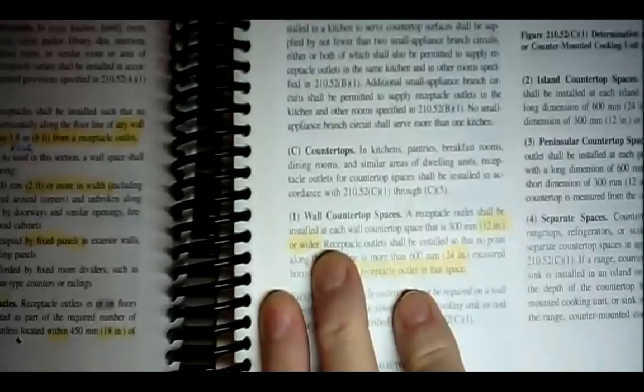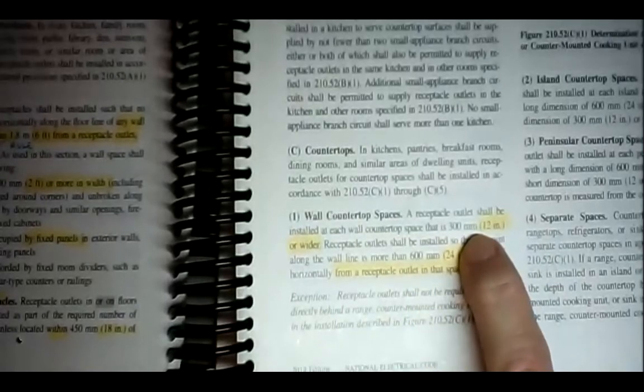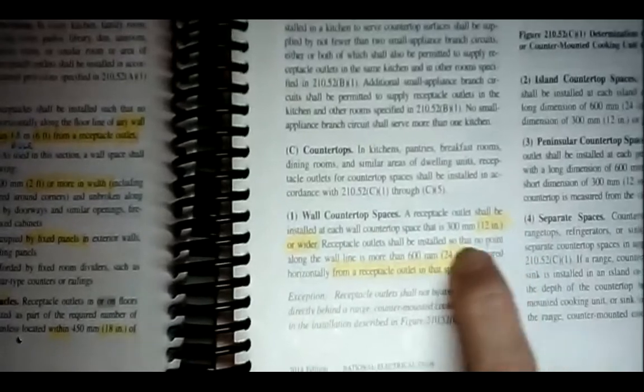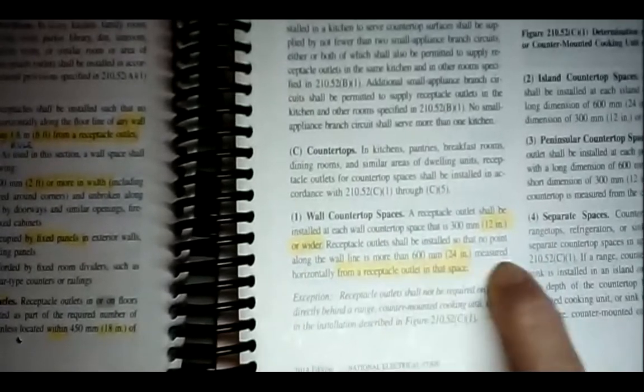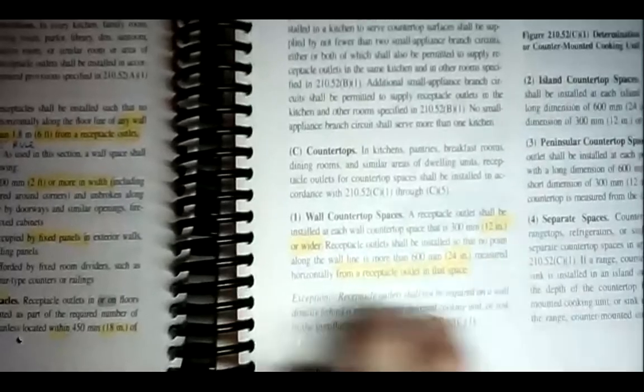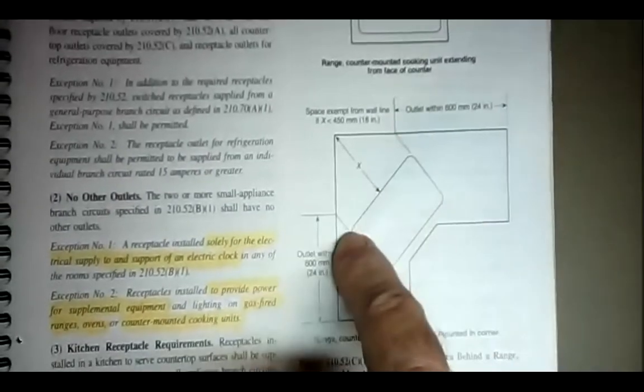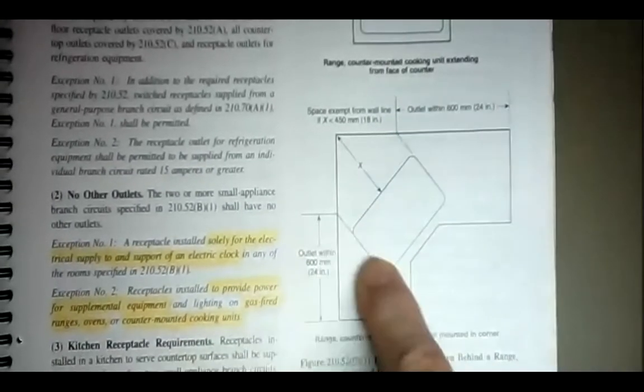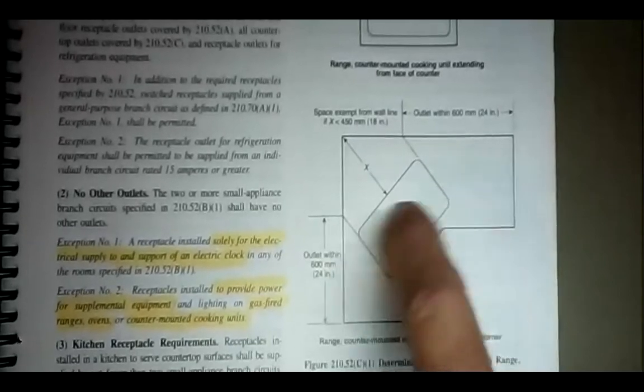A receptacle outlet shall be installed at each wall countertop space 12 inches or wider. Receptacle outlets shall be installed so that no point along the wall line is more than 24 inches — measured horizontally — from a receptacle. That's every four feet in the kitchen. Any wall space 12 inches or greater counts. You wouldn't put any behind a sink or a cooktop — they don't want you plugging in and reaching across a sink or a cooktop.